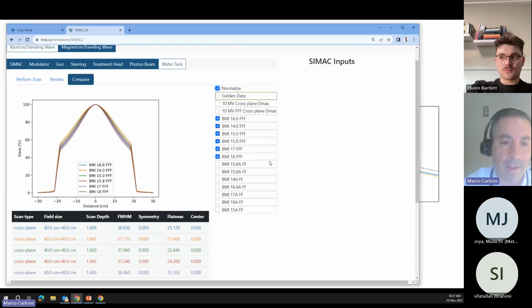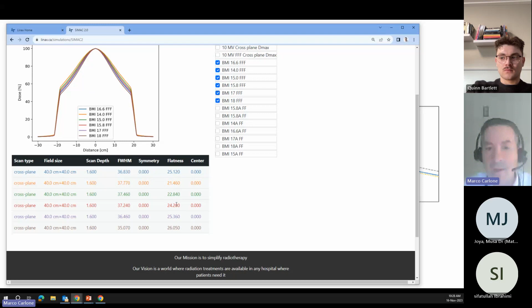Down over here we give some numbers on them. So we calculate flatness, although in the case of a flattening filter-free beam, the flatness is different than we'd expect. On a flattened beam, we'd expect this to be around 1, because we want very small deviations in flatness. For these beams, the flatness is very different because by definition they're unflat, and you do see some number changes that we calculate. This is just a standard flatness calculation of the maximum dose minus the minimum dose within the 80% range of the profile. So you can see we calculate quite different numbers, which are quite a bit different than you would have on a depth dose measurement.